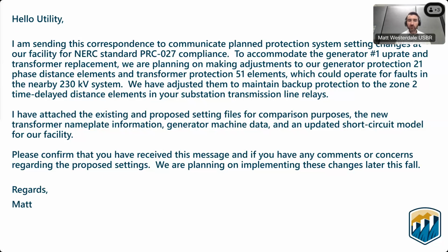Then we also provide a quick summary of the changes we're making and why we're making them. So we're indicating that we're performing an uprate on our generator and also a transformer replacement, so they know to update their short circuit models. Then we're telling them what protection elements we're changing, and indicating that we're trying to maintain the protection and just adjust it for the existing changes.